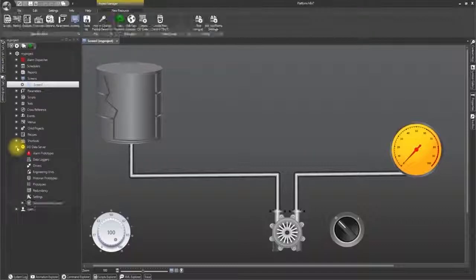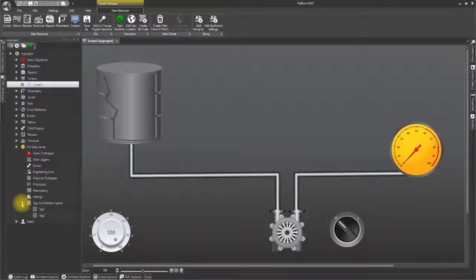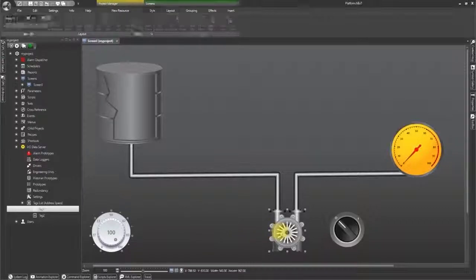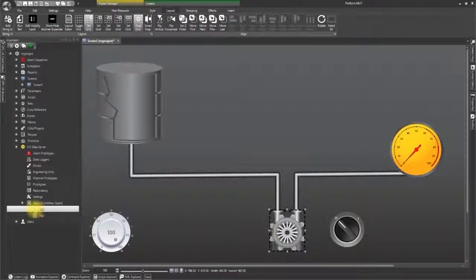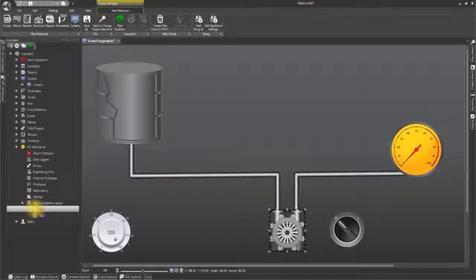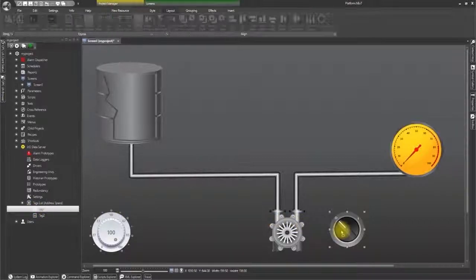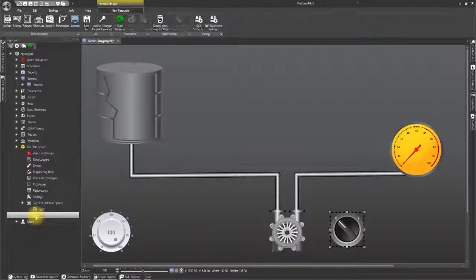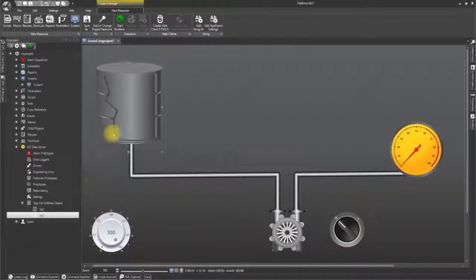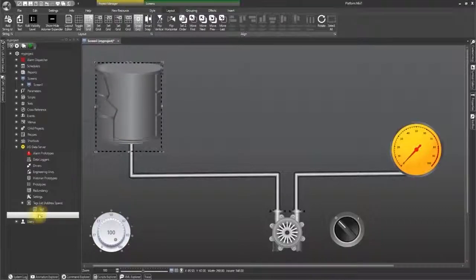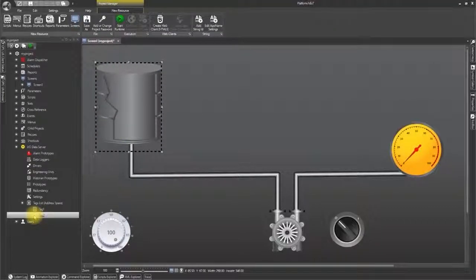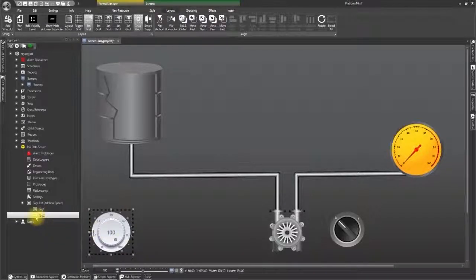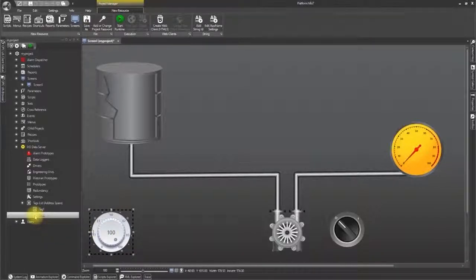Open the IO data server resource. Open the tag list I created beforehand and click and drag tag 1 onto the pump. Select it again, but this time drag and drop it onto the selector switch. Now select tag 2 and drop it onto the tank. And then select tag 2 again and drop it onto the knob. And do the same for the meter.